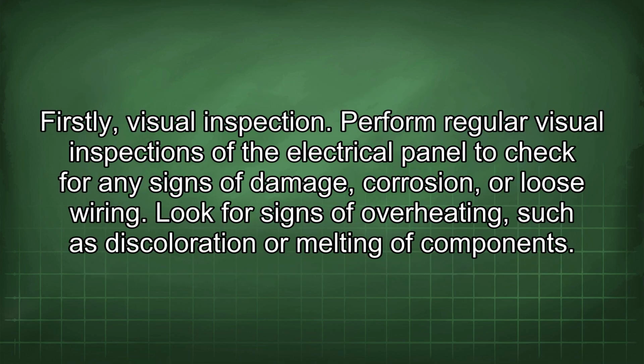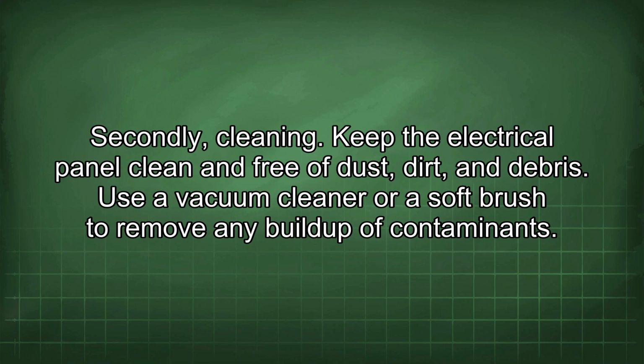Firstly, visual inspection. Perform regular visual inspections of the electrical panel to check for any signs of damage, corrosion, or loose wiring. Look for signs of overheating, such as discoloration or melting of components. Secondly, cleaning. Keep the electrical panel clean and free of dust, dirt, and debris. Use a vacuum cleaner or a soft brush to remove any buildup of contaminants.